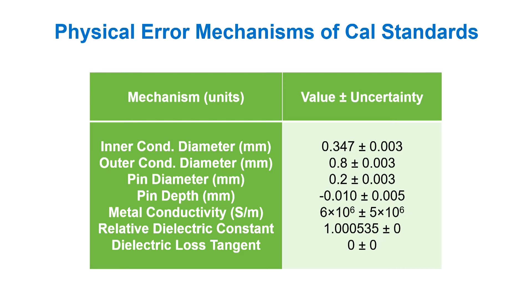So let's just look at some of our physical error mechanisms for our cal standards. For the 0.8 millimeter, we've got inner conductor diameters, outer conductor diameter, pin diameters and pin depths, et cetera. And ideally, what we'd like is to have all of our dimensional tolerances traceable to NIST measurements in Gaithersburg, but for this particular new kit we have, we don't have that, so we're utilizing the dimensional tolerances that were given to us by Anritsu to create our models.